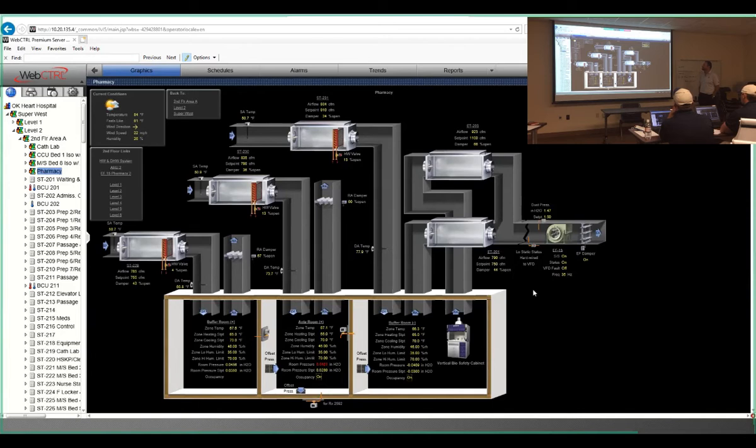And maybe you guys should definitely learn from our pain and suffering. One of the challenges we had in getting this space to operate was the air handler ramping down, right? We have a mix of pressure dependent and pressure independent systems within here. What that means is these return air dampers that are feeding the buffer room and the ante room are what is controlling to maintain that pressure.